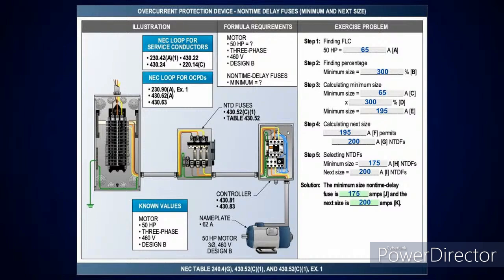And one thing I've started with, like I've done every one of these, is I always reemphasize the rule of thumb one more time. If you're sizing your overcurrent protection device at 125% or less, go up to the next standard size. Once you get over that 125%, then we're going to drop down to the next standard size. The only places you're not going to have that is where I have to protect the conductor, which is sized at 250% for phase converters, and then also transformers. But we went over that last week and the week before.